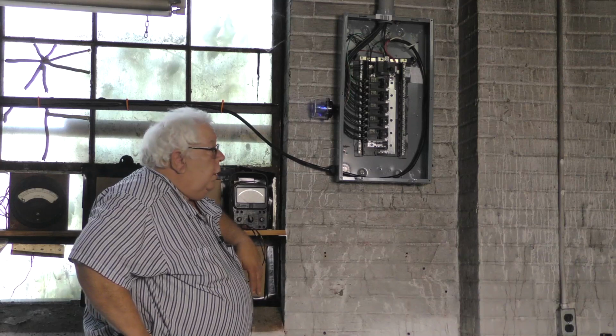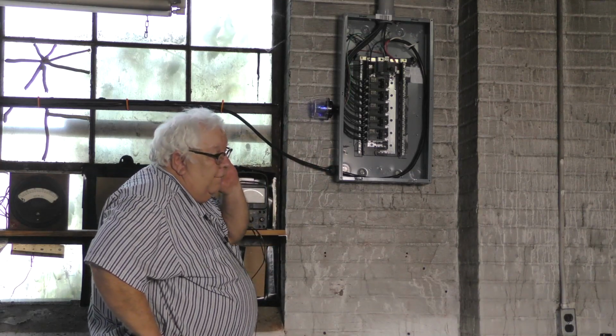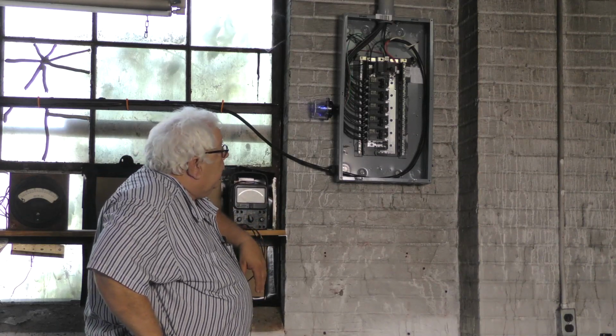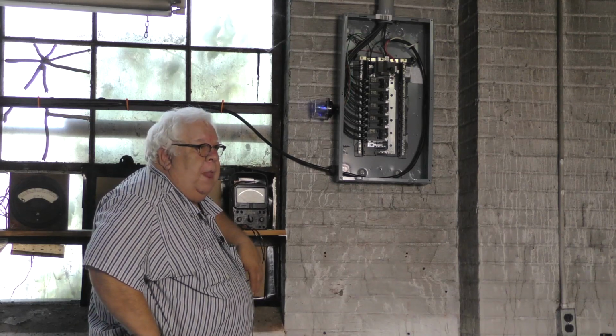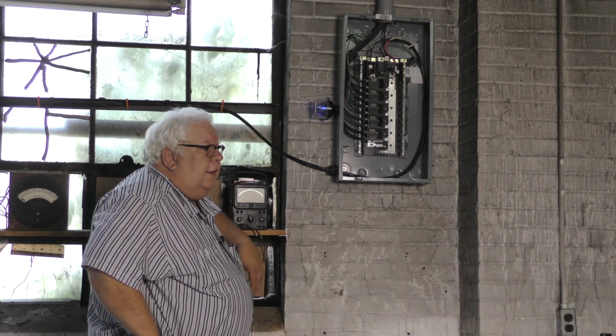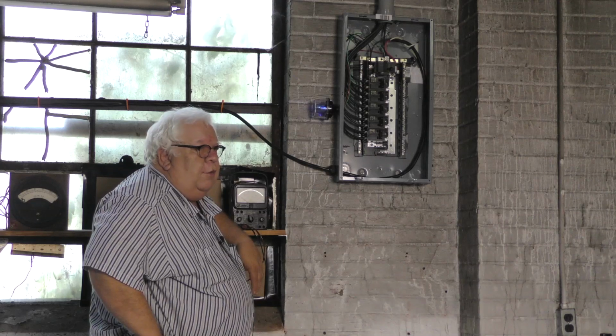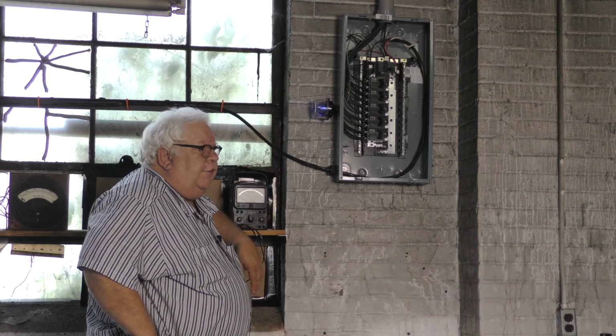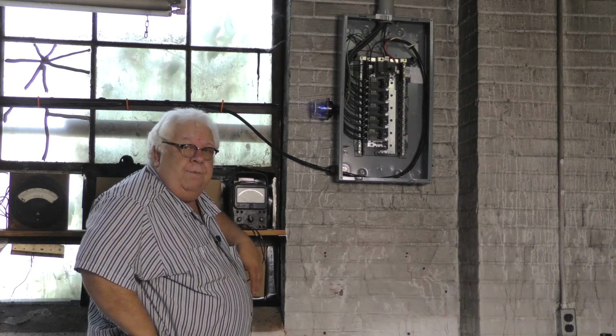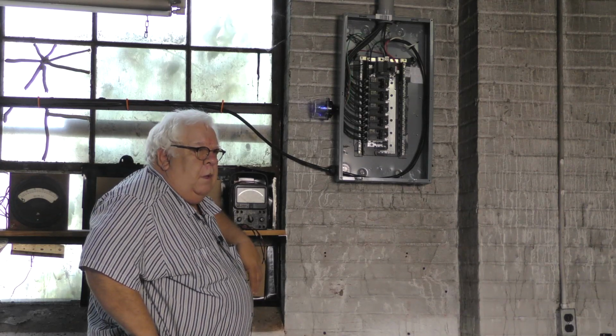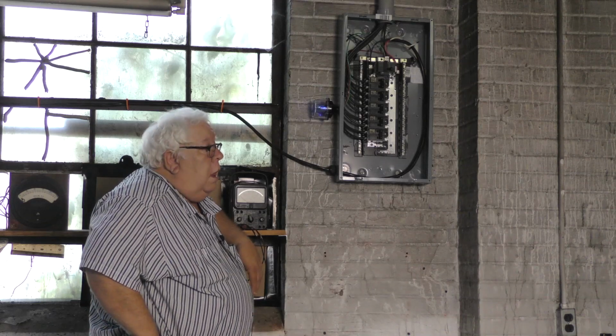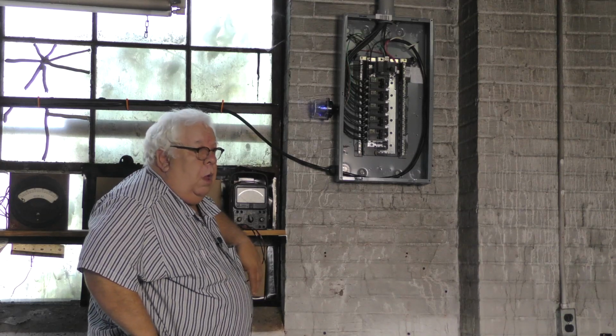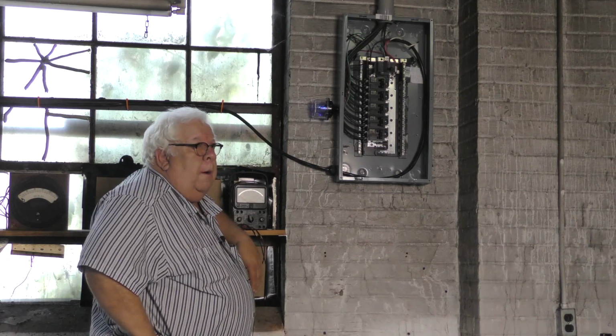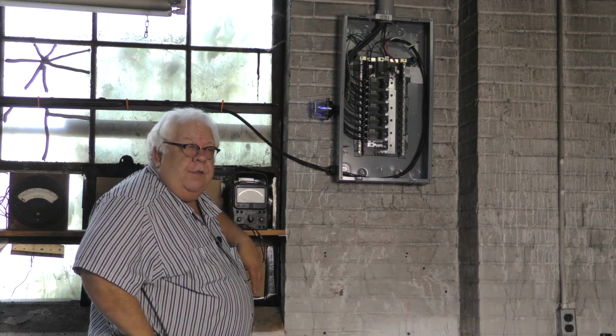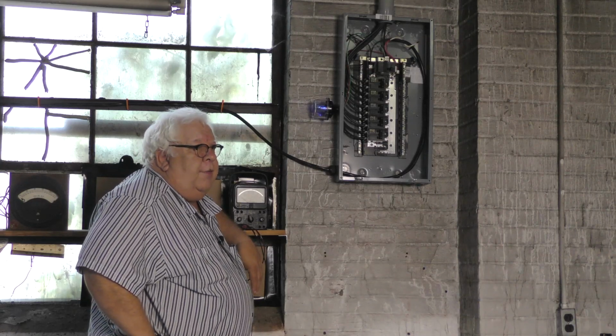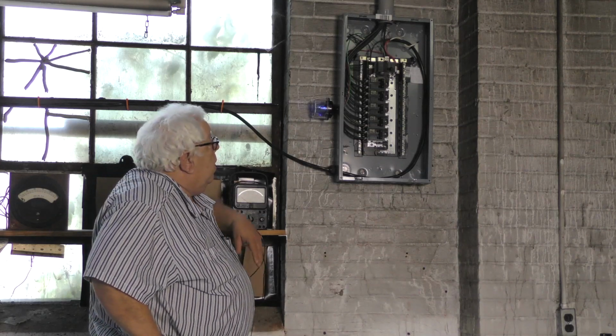Just by way of review, I wanted to show you our Enphase combiner panel. This is actually not an Enphase panel, it's an ordinary loads panel. We bring down 5 pairs of cables from the roof. They're not Enphase cables even, they were actually DC cables before, and we just reused them. But we could use regular house wiring for this. We're only going to generate about a few amps, 6 or 8 amps per circuit. We have 8 panels with Enphase IQ7Xs on them, 1 on each, wired with 2 wires for the 240 volts AC. That's what you get out of an Enphase. There's no neutral. And then we brought down a ground, tying all the panels together, that ties into this panel.